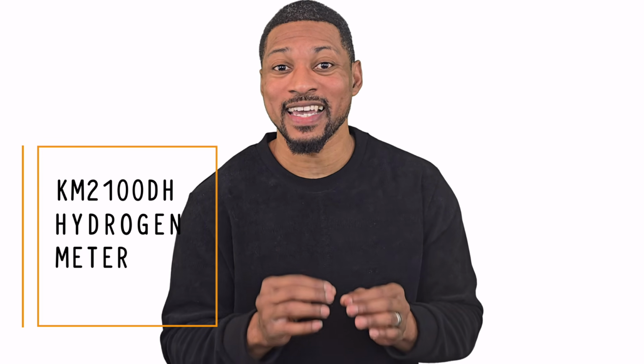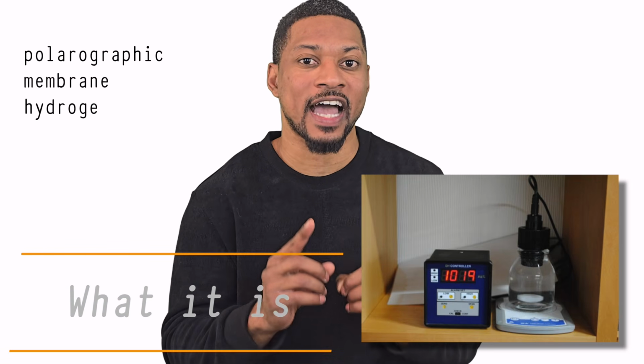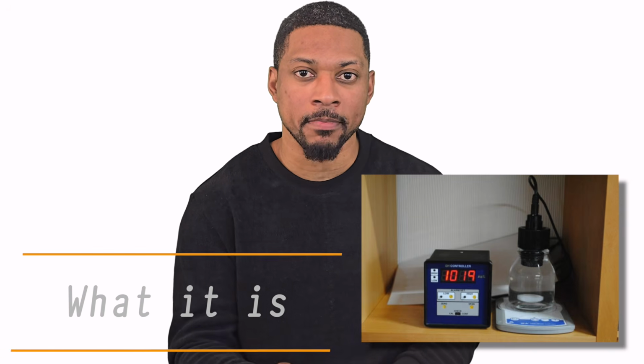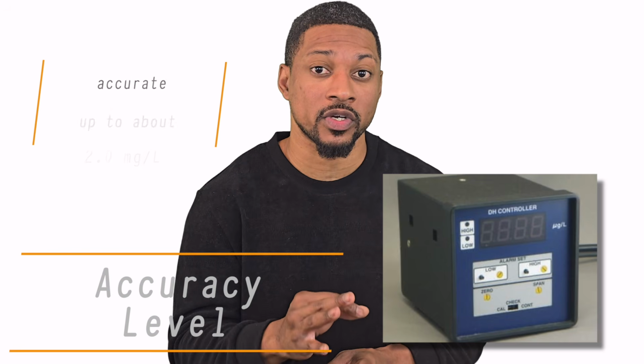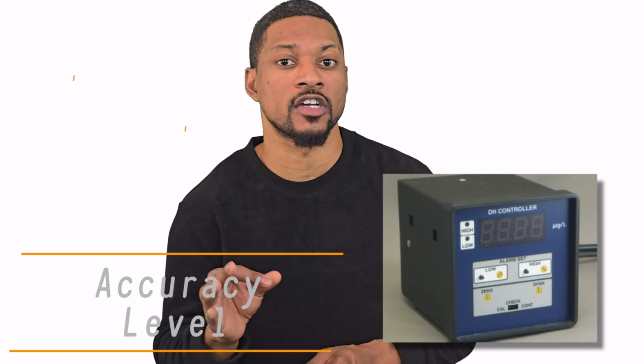Now let's talk about a popular mid-tier tool, the KM2100DH. This is a polarographic membrane hydrogen electrode. It uses an electrochemical reaction behind a membrane to detect hydrogen. When calibrated correctly, it can be reasonably accurate up to about 2 milligrams per liter. Above that, the device really isn't accurate.